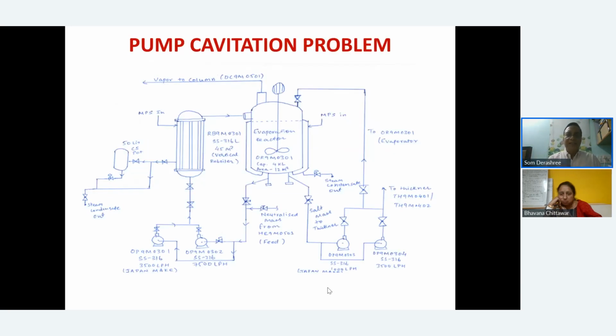This is another very typical case in the process industry. There was a lot of vibration taking place here. What is here is a reactor, actually a reactor bottom. The product is taken out here from the column at a defined rate, so this level is maintained here. To maintain this level, the neutralized mass is put in at the suction of these pumps. These pumps pump through the heat exchanger. There is steam put in here, and then after heating it goes and gets flashed, and that is how it is maintained here. So as the level goes down, this operates.